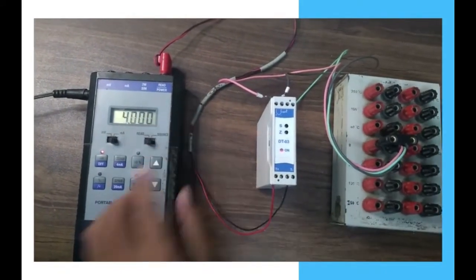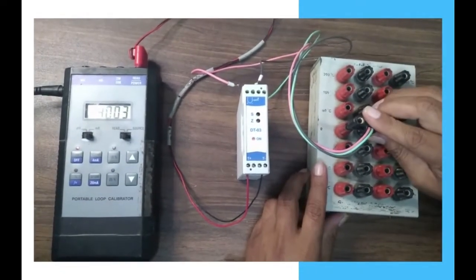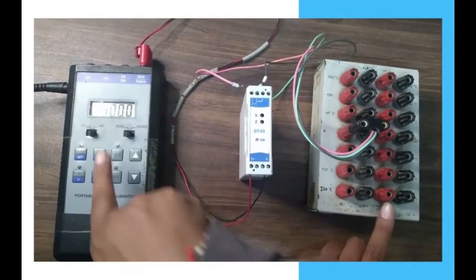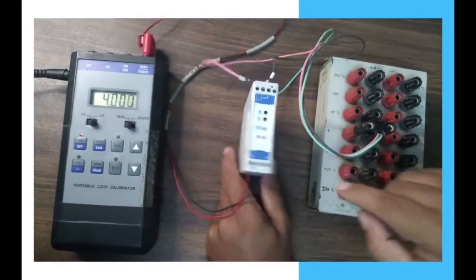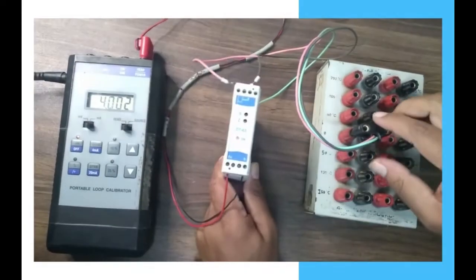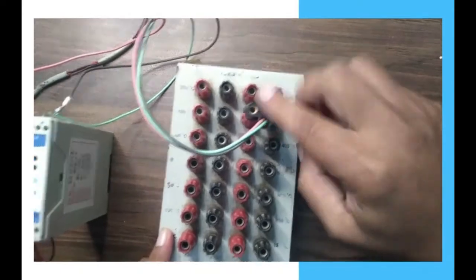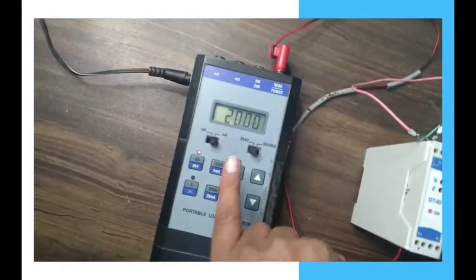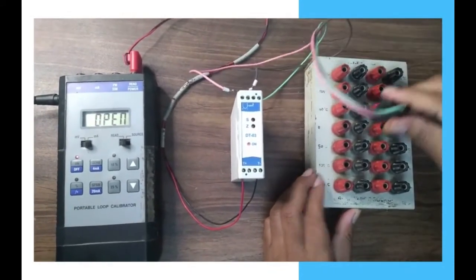Our temperature transmitter full range is 0 to 300 degrees Celsius. So when I apply zero at the resistance source, we will get 4 milliampere current in the calibrator. And when I apply 300 at the resistance source, we will get 20 milliampere current in the calibrator. This is how you can see the current changes according to the temperature.